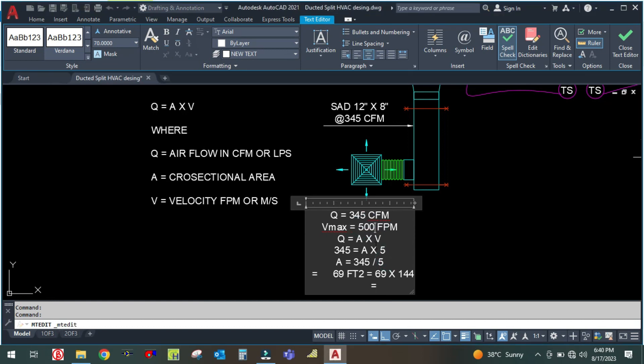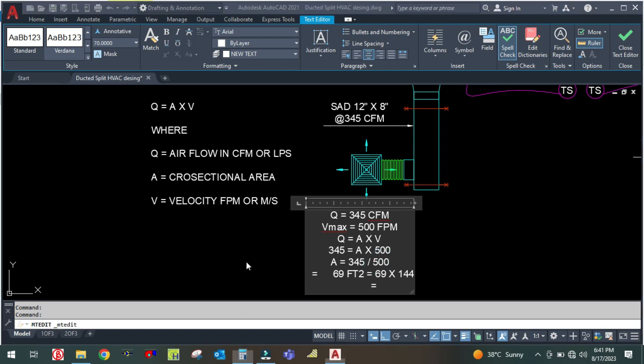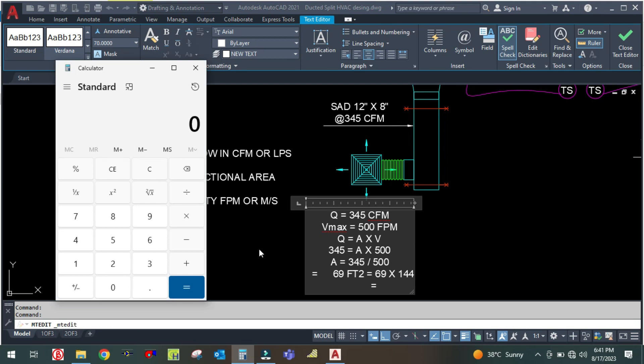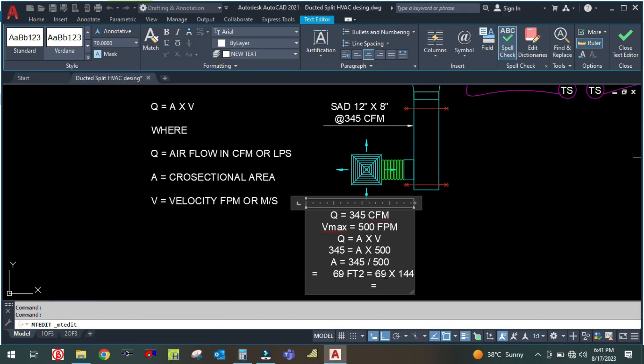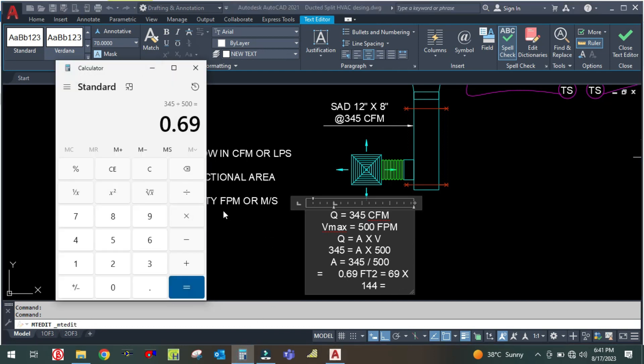The maximum velocity for the diffuser is 500 feet per minute. So you place 500 here and divide 345 by 500, giving 0.69 square feet. You then multiply by 144 to convert to square inches.